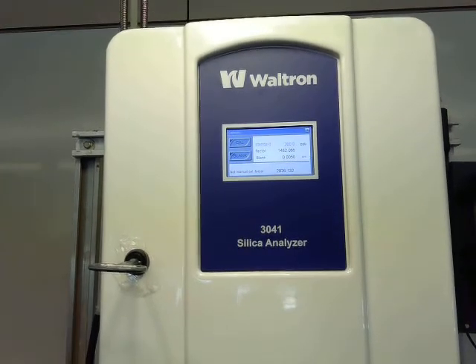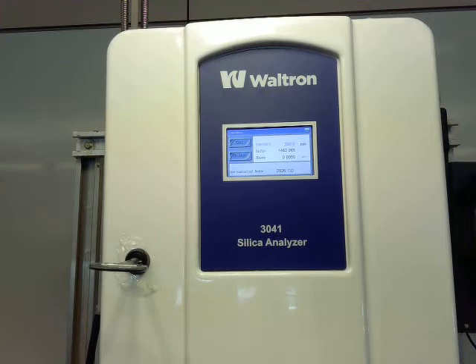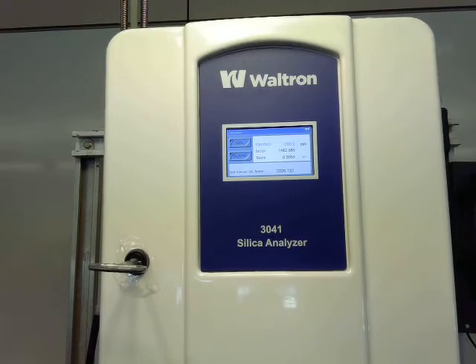And again, if our calibration factor was outside the range that the analyzer considers good, this screen would be flashing. You also have a calibration failure alarm on the main screen. And again, it doesn't mean you can't run the analyzer. It would continue to run with the last good cal factor that it had. But you can't get rid of that alarm message unless you do successfully pass a calibration.